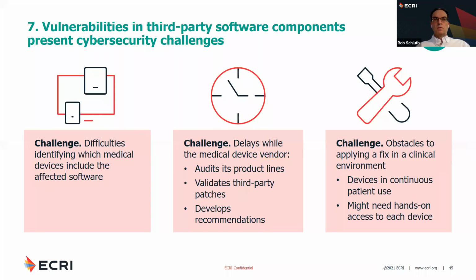So we've already talked about how hard it is to just know if your medical devices have software that's affected. Another challenge is what the vendor has to deal with. A manufacturer has to first audit its product line to figure out, okay, which of our products include the software that has a vulnerability. Then when a patch is available, they need to validate it to make sure that the patch, the fix, doesn't end up causing some sort of problems in how the medical device functions. And then they need to develop recommendations that hospitals can use when they're implementing the fix. So all that takes time and can lead to some delays. And that's before you even get it to the hospital.